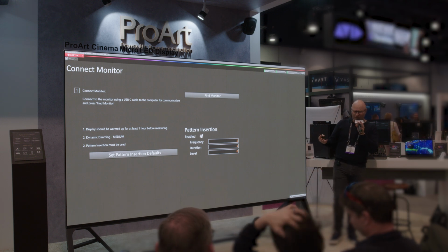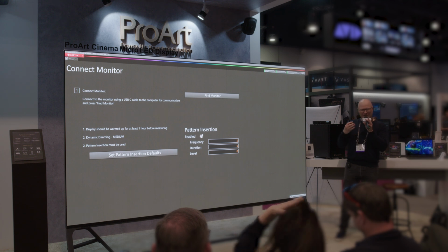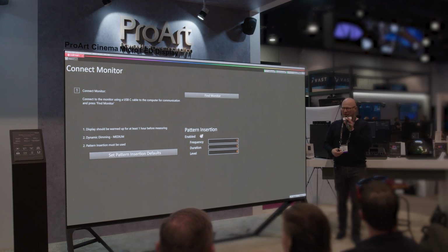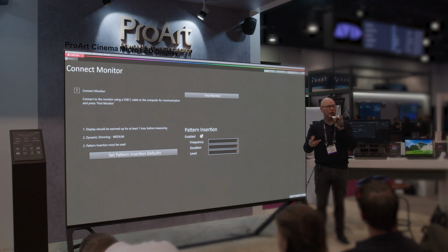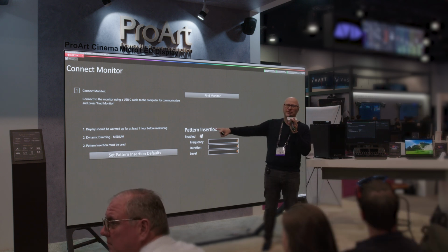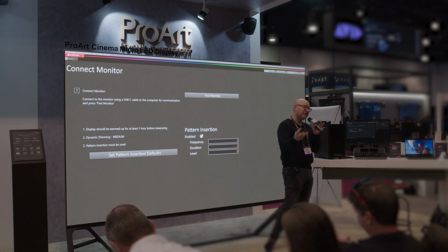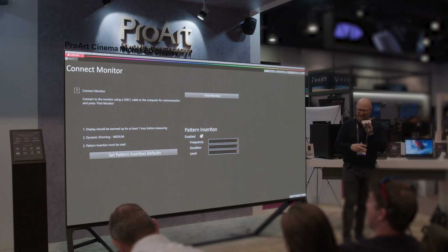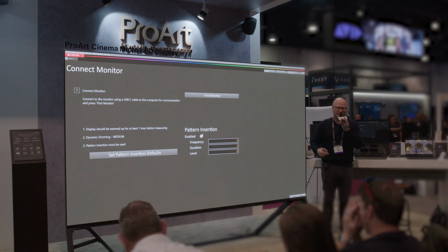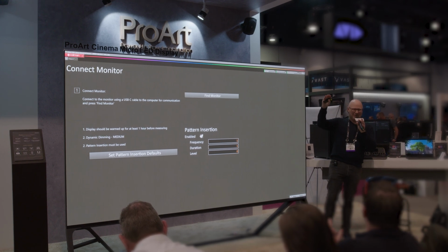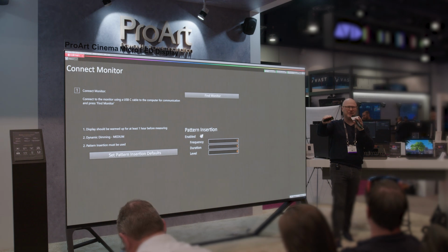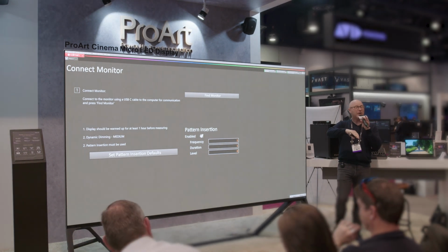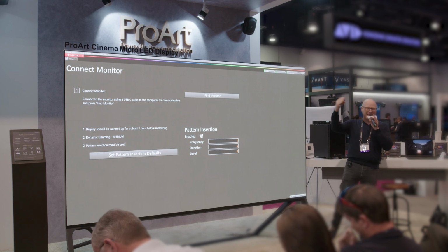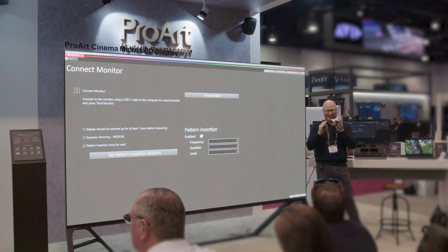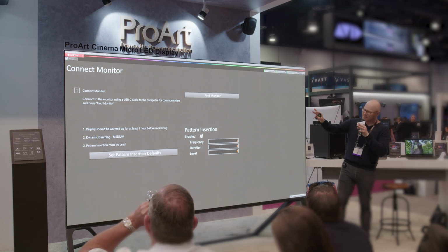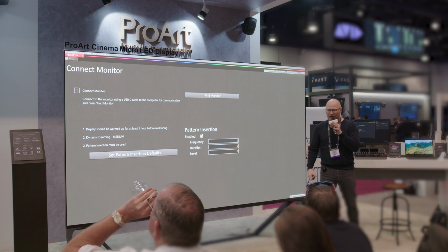Now, on an OLED, such as the PA32DC, OLED technology likes to have image retention. So, so that we don't burn in the monitor or ruin it during the calibration process, we put a pattern insertion into the process. It's going to put up a patch, then give the monitor a little bit of a break so we don't overheat it. If you've worked much in HDR, most HDR is not all the way up at the peak. The vast majority of HDR is at that lower 200 nits and below. But when we calibrate, we want to go all the way up to that peak. We want to hit that 500 nits, that 1,000 nits, that 2,000 nits. But we also know we don't want to stay there too long because we don't want to burn these things out. So we put in this pattern insertion so when we make those measurements, we're not going to ruin the monitor.